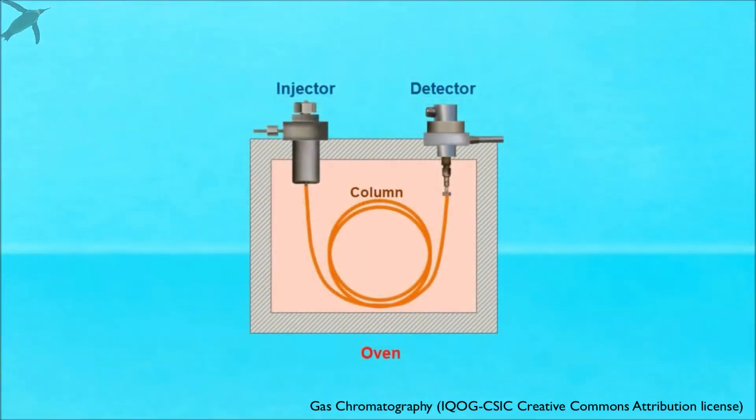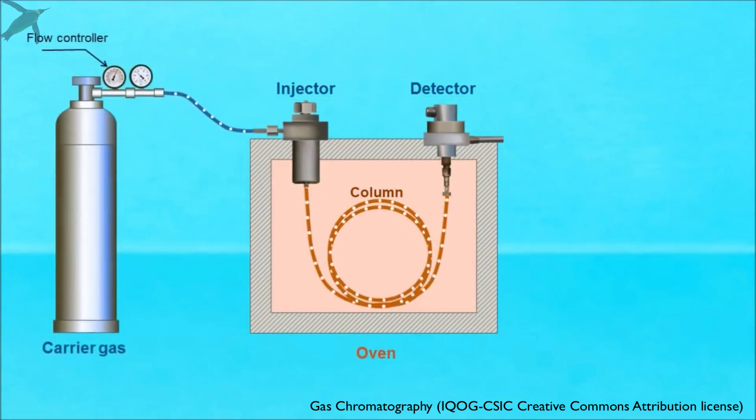The gas chromatograph is essentially a temperature-controlled oven that contains the column. At the beginning of the column, there's an injector, where you inject your sample via syringe, and at the end of the column, there's a detector that detects your peaks. Upstream of the injector, you have a tank of carrier gas, normally helium, that through a flow controller, provides a steady stream of carrier gas through the whole system.